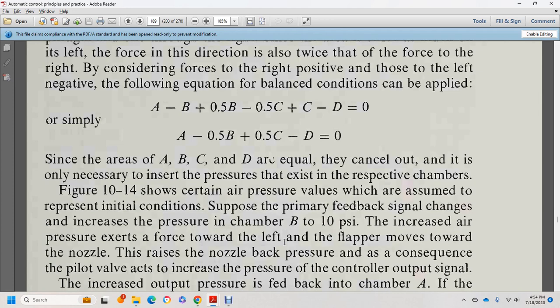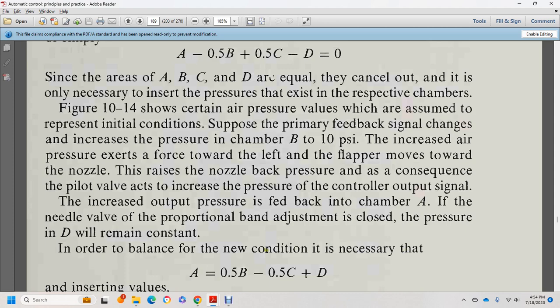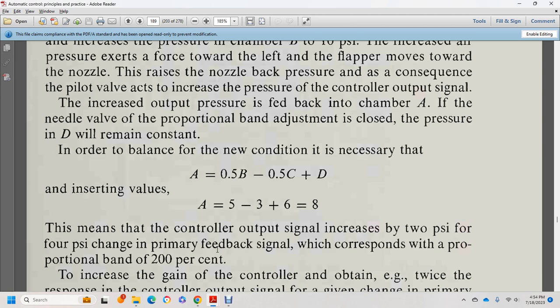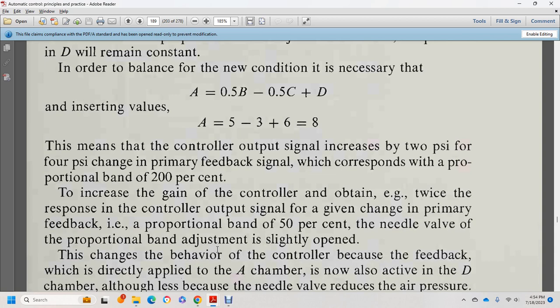Assuming the primary feedback signal in chamber A increases, raising pressure B to 10 psi — the increased air pressure exerts a force toward the left and the flapper moves toward the nozzle, increasing nozzle back pressure. The pilot valve consequently increases the control output signal. If the needle valve for proportional band adjustment is closed, pressure D remains constant. The new balance condition requires: A = ½B − ½C + D. Inserting values: A = 5 − 3 + 6 = 8. This means the control output signal increased by 2 psi, and a 4 psi primary feedback change corresponds to 200% proportional band.